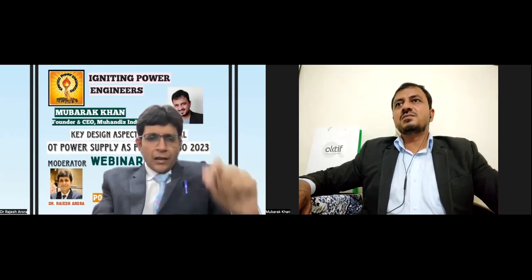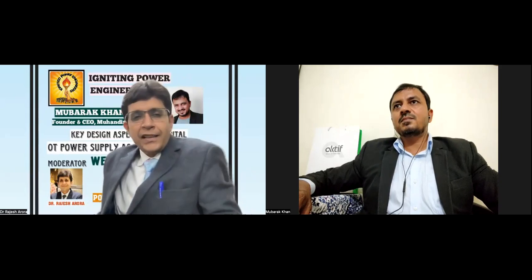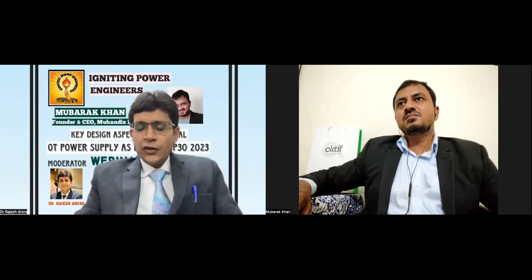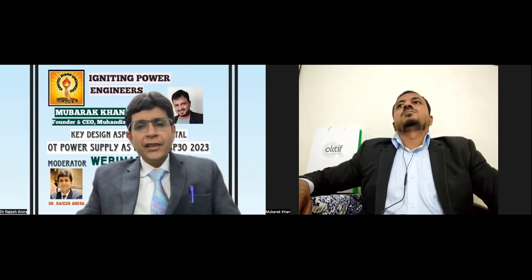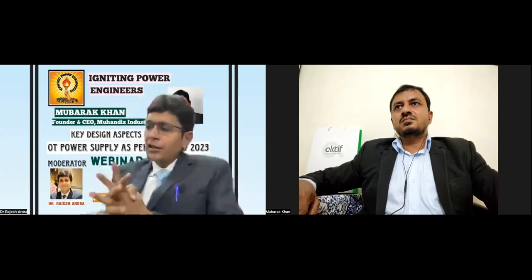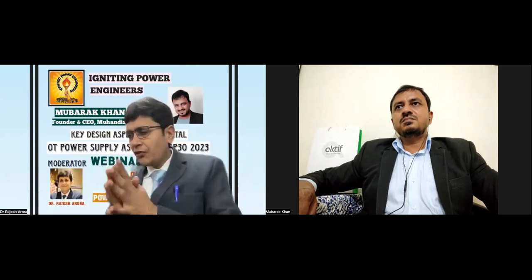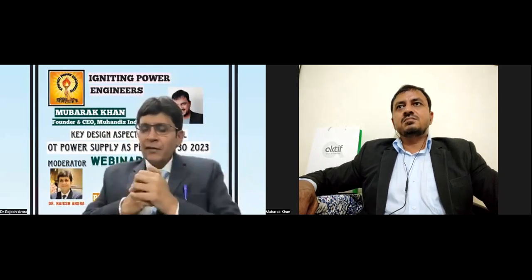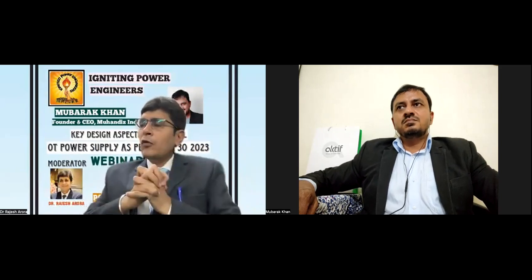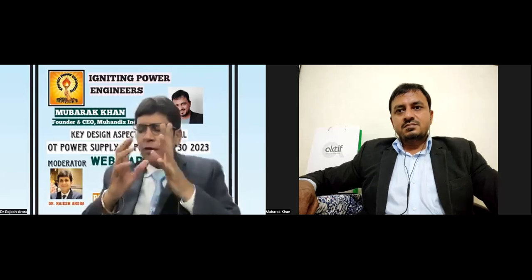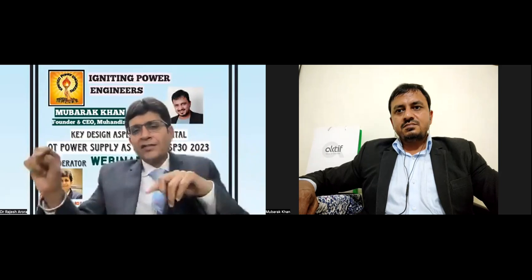Yes, Ajay. Sir, I would like to elaborate on that. I will throw some light. The question was very valid: what happens when the second fault happens? In hospitals, especially in the ICU and operation theater, usually only a single phase system is used. In a single phase system, first comes the isolation transformer, which is as per IEC 61558-2-15, already explained very well. Then there is an insulation monitoring device as per IEC 61557-8. In that transformer, so many feeders are there.